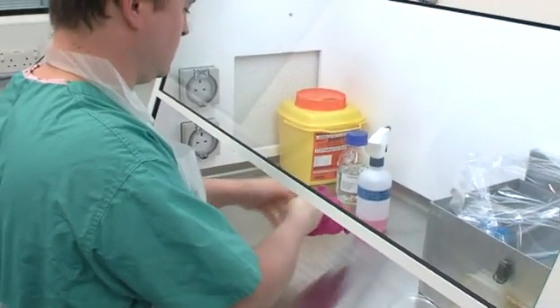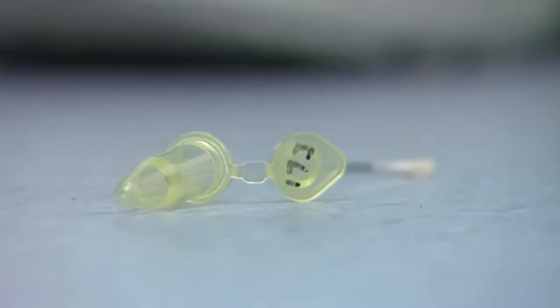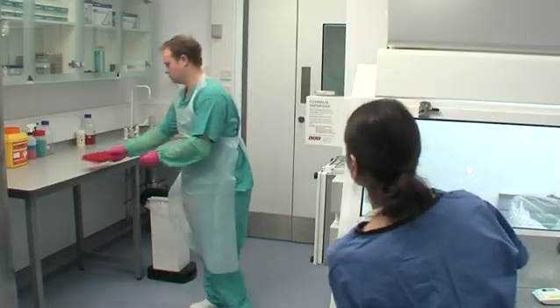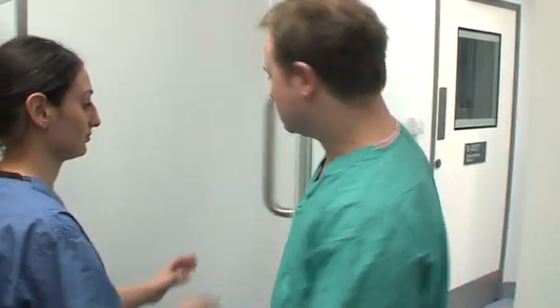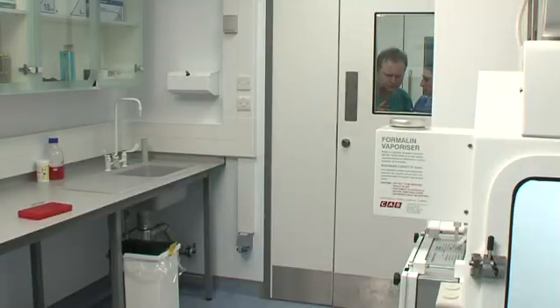Risks to other samples within the cabinet should also be considered. A small spill outside a safety cabinet of a Category B virus might include a swab, a feather or a small piece of tissue. Given the risk factors, the following procedures should apply. Alert all staff working within the area to move to another lab or lobby immediately. Prior to leaving the room where the spill has occurred, lab staff should remove any PPE. Relocate to a new area in the facility that's against the gradient of air pressure and assess what actions need to be taken. These will be listed in the risk assessment.